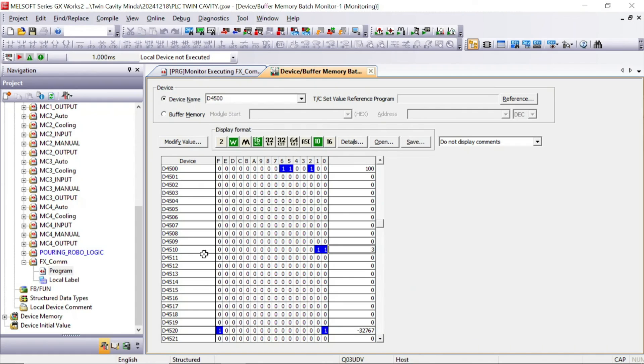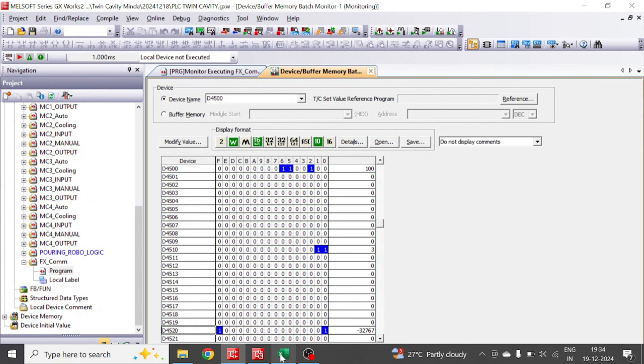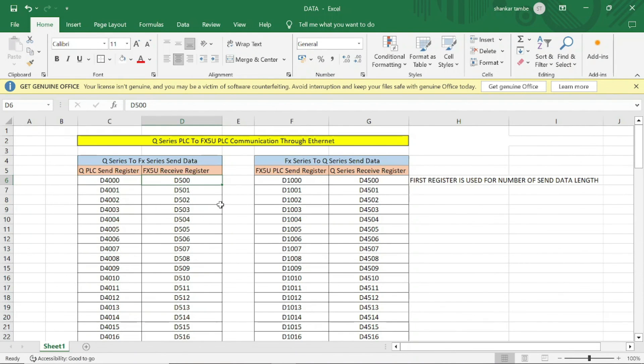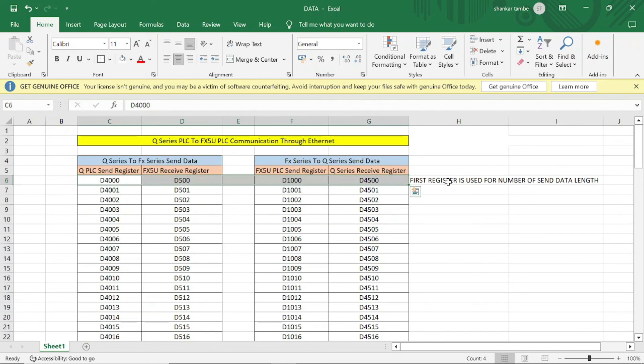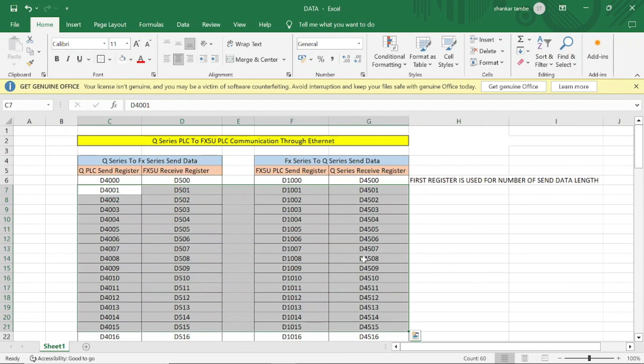The value is minus 32,767, and you can check the same in Q series — minus 32,767. In this way we have communicated Q PLC to FX PLC and FX to Q PLC. We exchange data from Q series D4000 to FX5U D500, and from FX5U D1000 to Q series D4500. The first register is used for the number of data length, so from this first register we move the number of data length. Thank you.